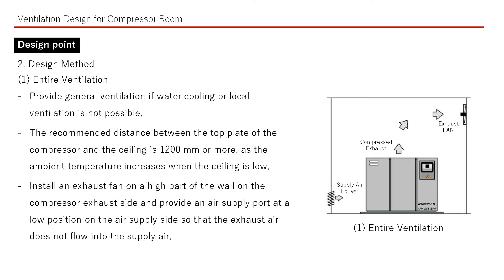First, about entire ventilation. 1. Provide general ventilation if water cooling or local ventilation is not possible. 2. The recommended distance between the top plate of the compressor and the ceiling is 1200 mm or more, as ambient temperature increases when the ceiling is low. 3. Install an exhaust fan at a high position on the wall on the compressor exhaust side, and provide an air supply port at a low position on the supply side so that exhaust air does not flow into the supply air.